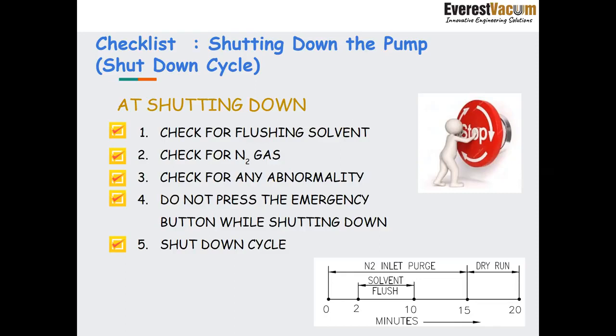Therein, we bring in the solvent flushing for another 8 minutes. That solvent along with the nitrogen keeps on entering the pump and cleans out the pump of any contaminants. Then we stop the solvent. Nitrogen still continues, the purpose being to make the pump completely dry from any solvent traces. In the end, for the last 5 minutes, when the nitrogen purge has also been stopped, there is only the dry run of the machine. This ensures that the pump is now completely cleaned of any contaminants and solvent traces, and it is fit for use when it is again brought into operation. So this is what the average shutdown cycle looks like and what it does.